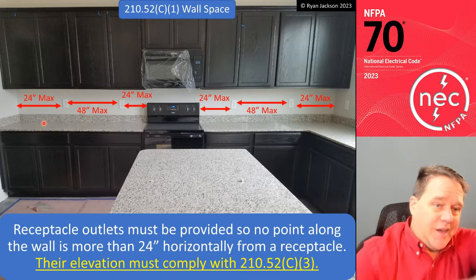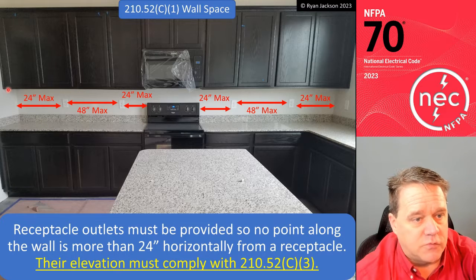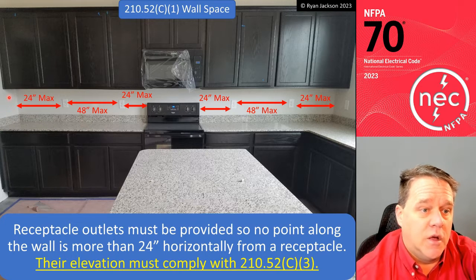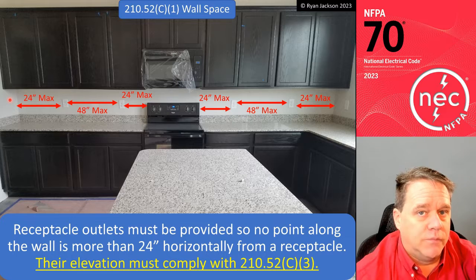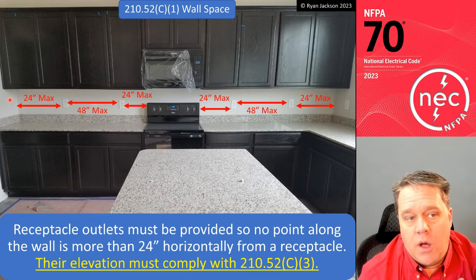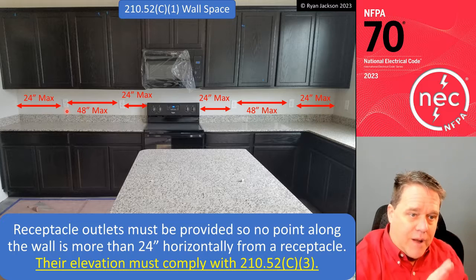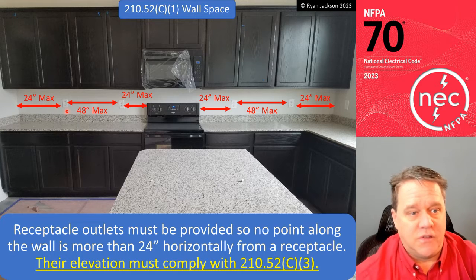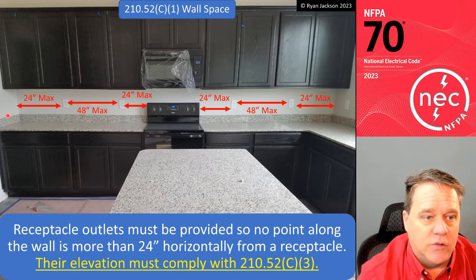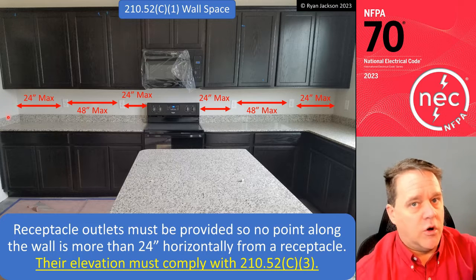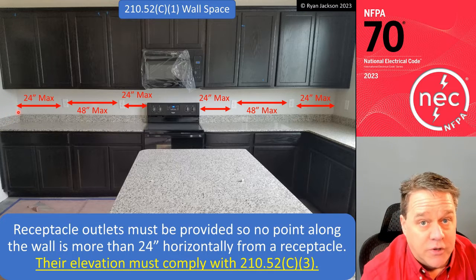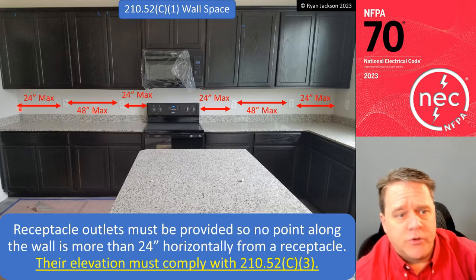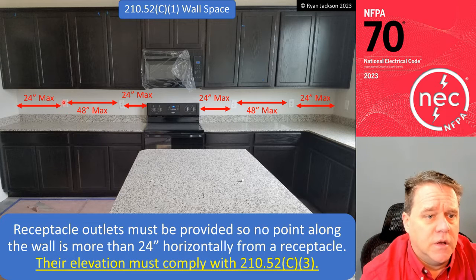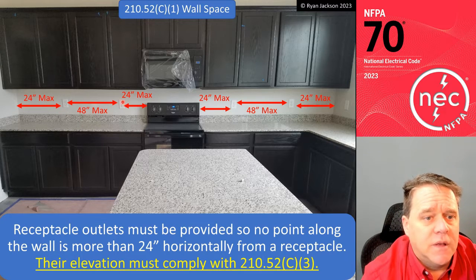The wall that my elbow would be smacking against right over here where my mouse is, do I need to count that wall? In my opinion, no. I think it starts where my arrow is, all right? So I don't think it wraps around the corner in this instance, okay? Because I don't think that little portion of wall is wall countertop space. So we're going to butt our tape in to the left, pull it to the right, receptacle within 2 feet. Pull the tape 4 feet, add another one, right?